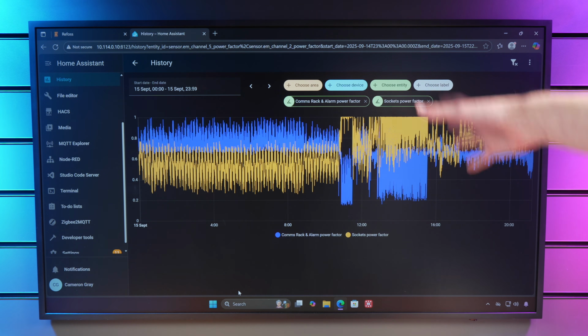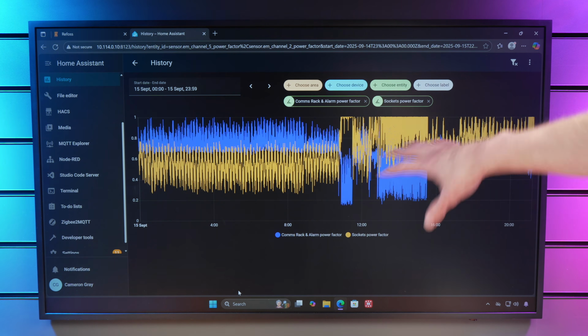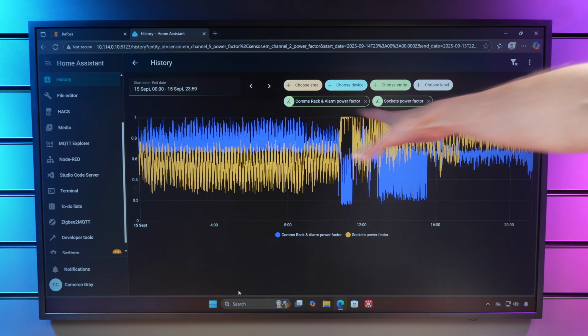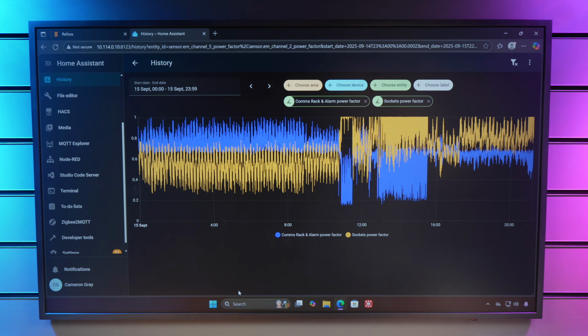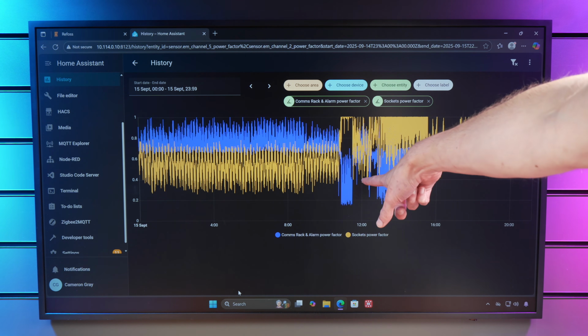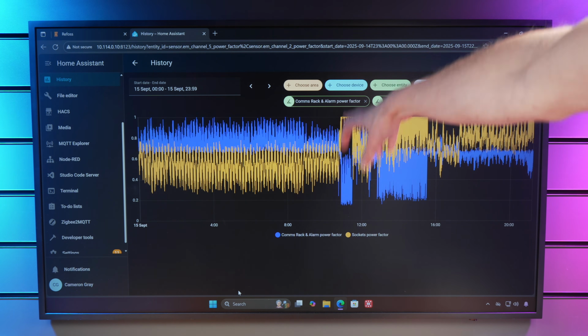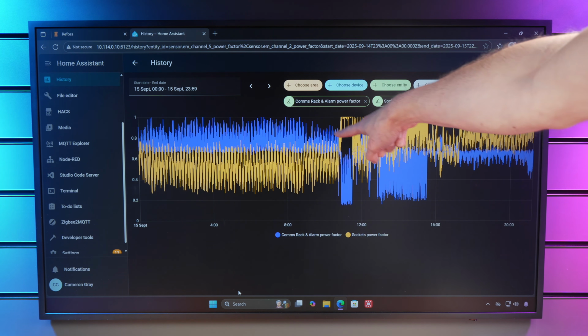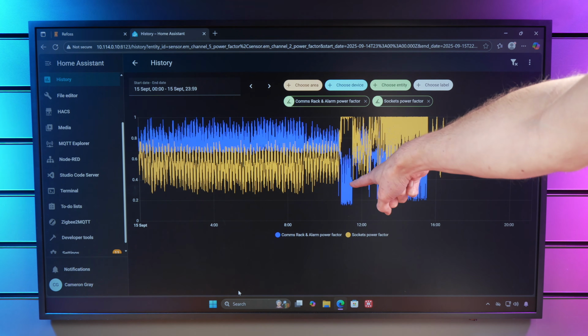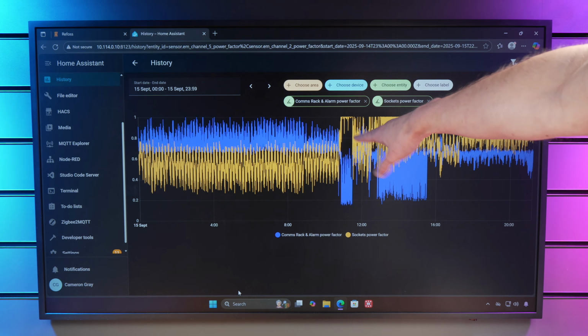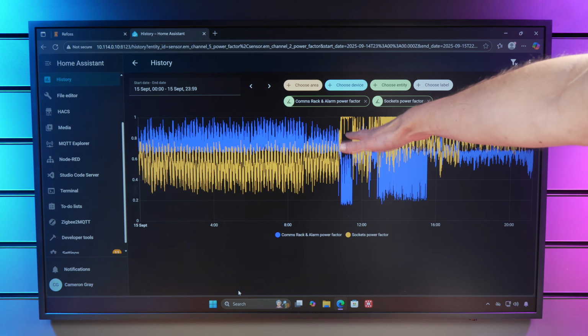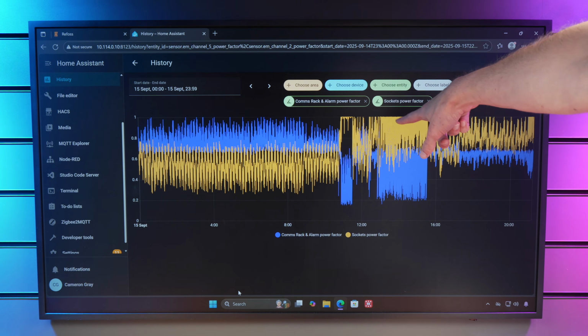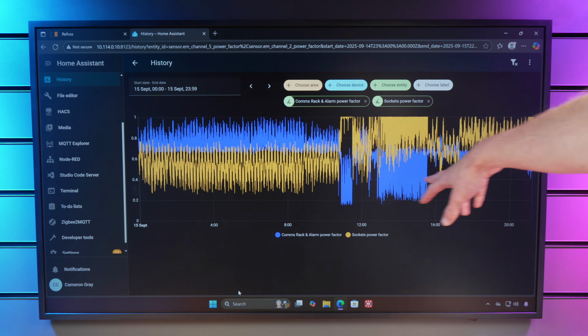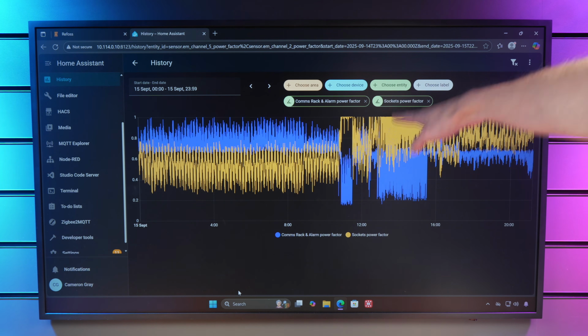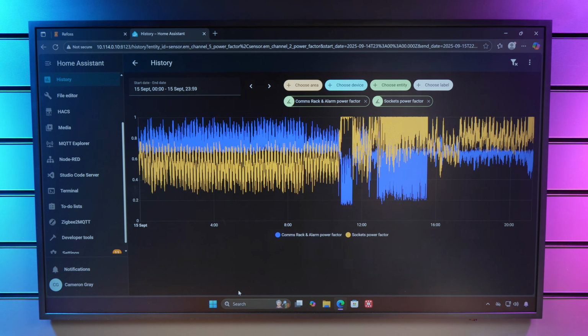Now, that would be expected, and even with the fluctuations there, that's still what I'd expect. But now look behind this at the comms rack. When the heating element kicked in on the socket circuit, the power factor being measured for the comms rack massively dropped down. Then it jumped up again when the power factor was veering around on the socket circuit again, and as soon as the drying cycle kicked in, again the power factor for the comms rack circuit started fluctuating and dropping down massively. And this is really, really strange.